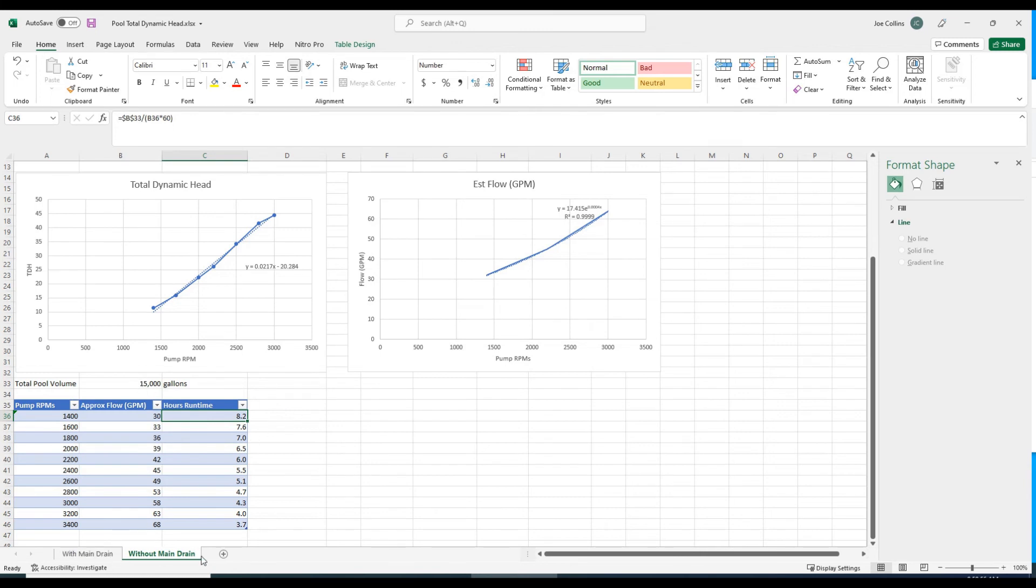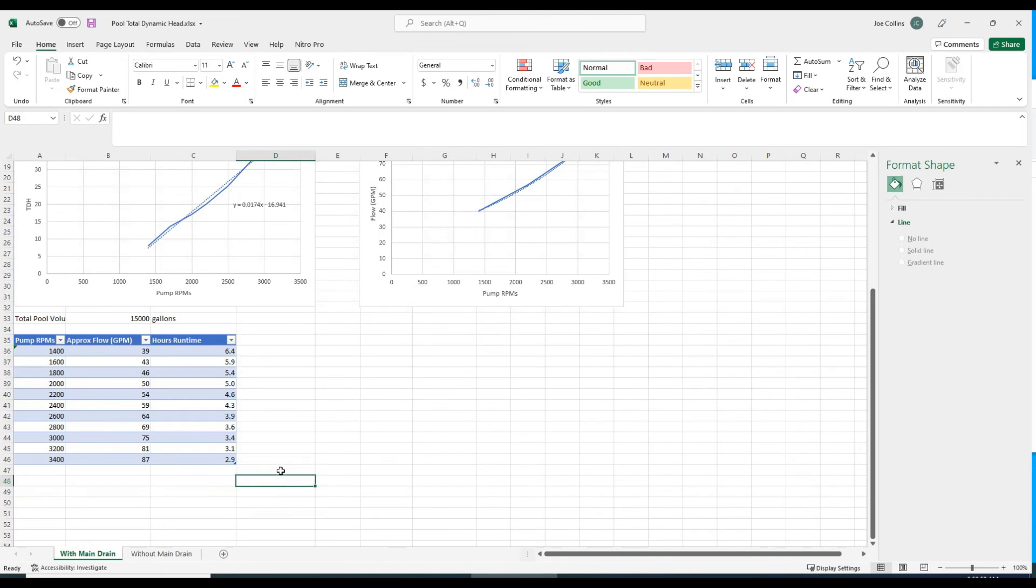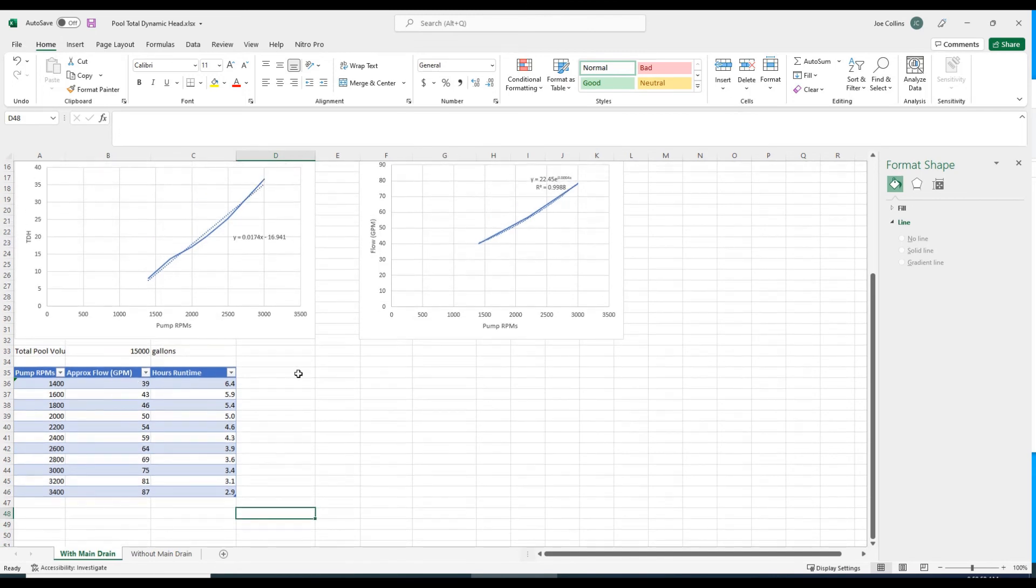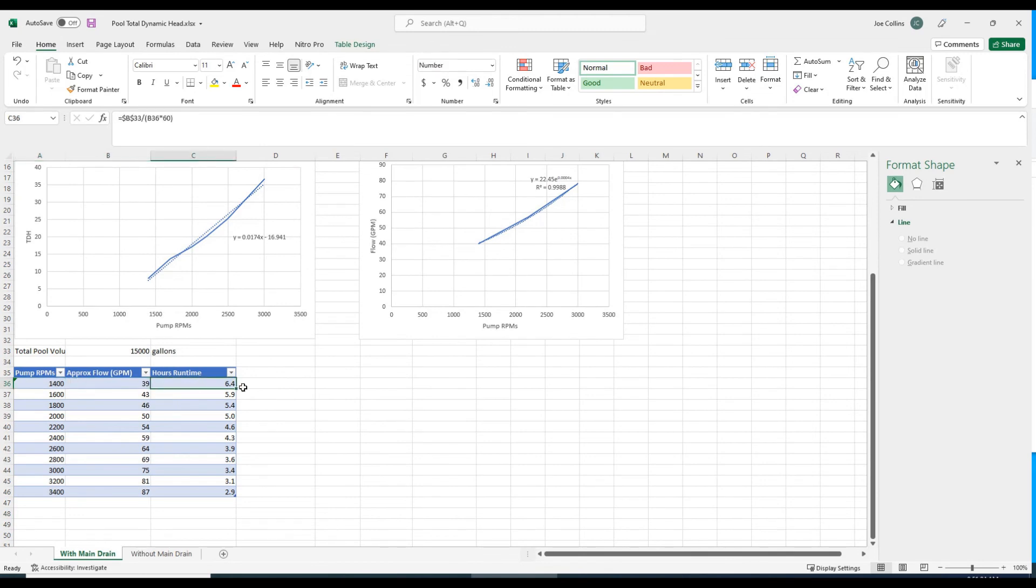If we go over to the previous tab with the main drain open, notice that number, because the performance is better with the main drain open and there's less head, that number drops to 6.4 hours.